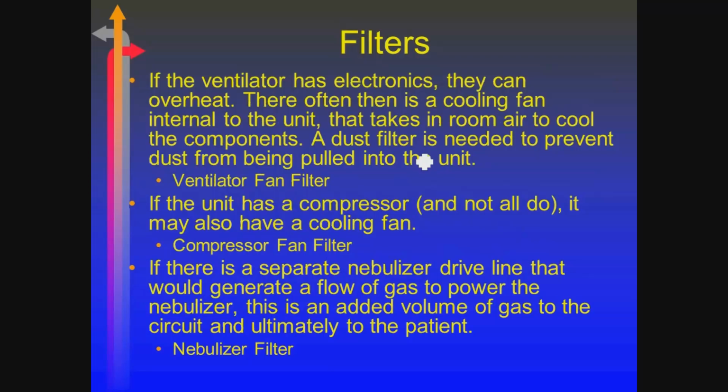There also is a fan filter that is present. So the ventilator, if you think about it, is this big electrical piece of equipment. It gets hot. So you need to have something to cool it down. But the air has a lot of dust in it. So you want to have some sort of a filter that removes the dust and other crud that's in the air prior to getting inside the unit. It's called a ventilator fan filter. And the same thing would be true if the unit has a built-in compressor. It'll have a fan filter also, and I'll show you that when we get in there. And then thirdly, if you're adding in some flow to power a nebulizer for breathing treatment, there could be a filter there also.